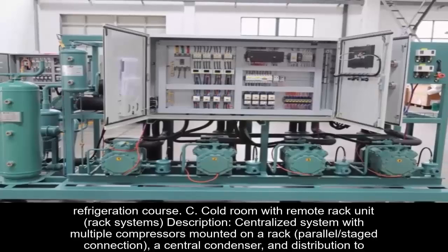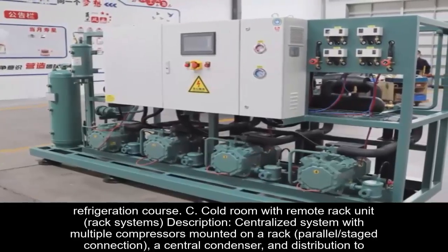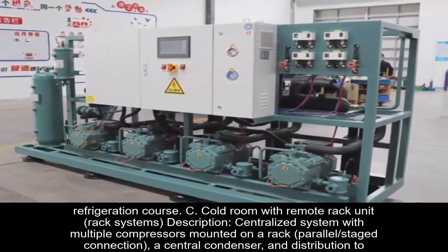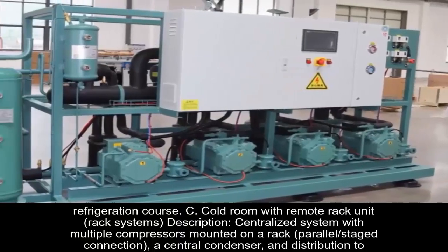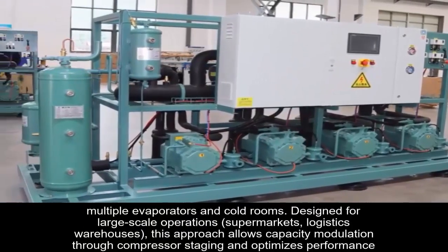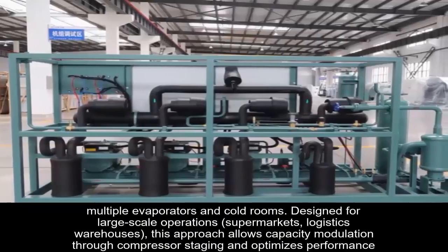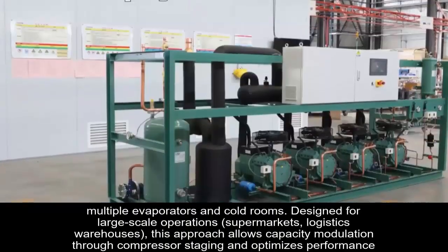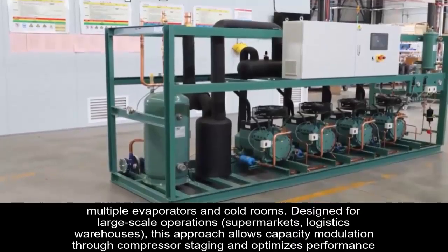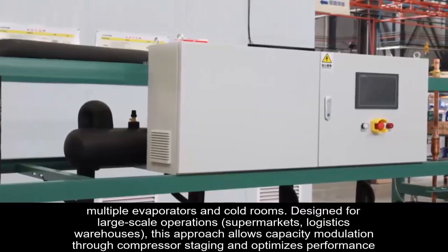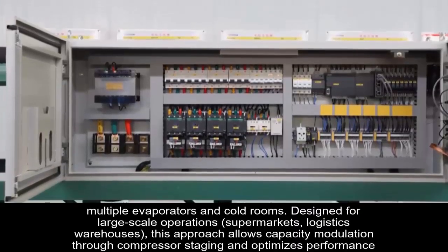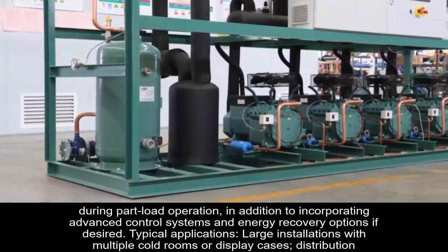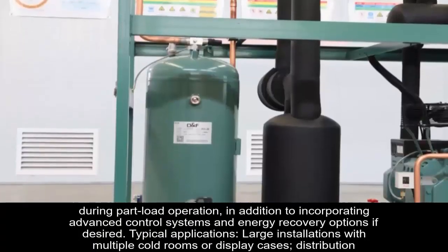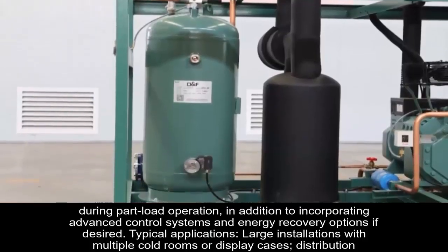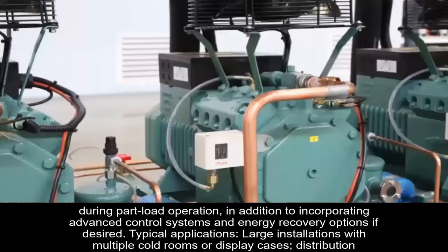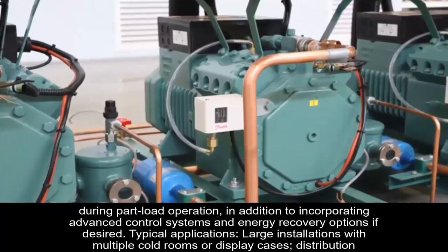C. Cold room with remote rack unit, rack systems. Description: centralized system with multiple compressors mounted on a rack, a central condenser, and distribution to multiple evaporators and cold rooms. Designed for large-scale operations, supermarkets, logistics warehouses, this approach allows capacity modulation through compressor staging and optimizes performance during part load operation, in addition to incorporating advanced control systems and energy recovery options if desired.